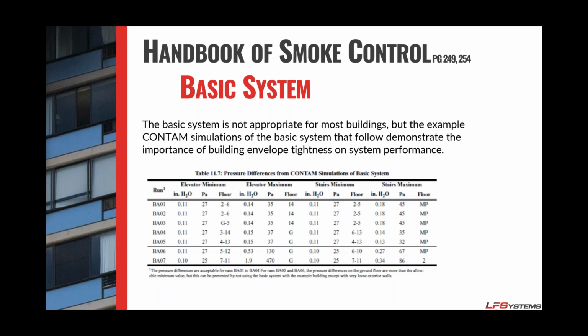That is, if you can get the doors open. Because if you look at the maximum pressure on 6 and 7, it actually is over ½ an inch of pressure on number 6 and almost 2 inches of pressure on number 7. So again, the maximum pressure that you want to maintain is a 0.25. If you exceed that 0.25, the mechanism on the doors actually will not open. It sees it as a blockage and a safety mechanism to where it will not open.